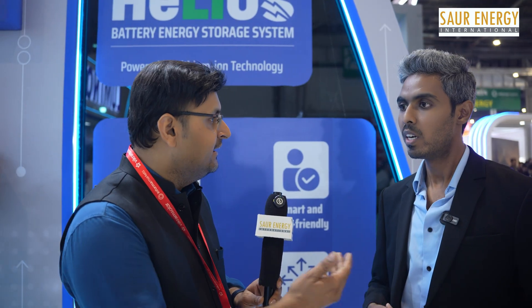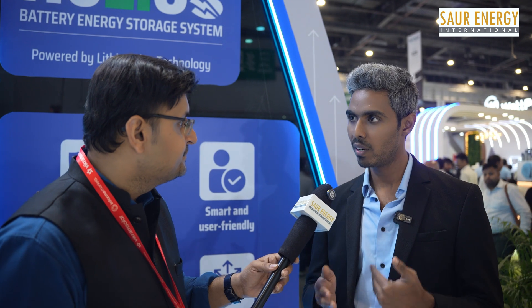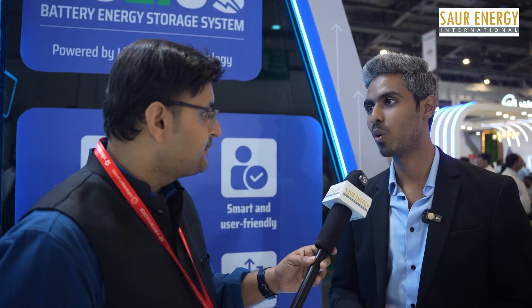For the residential and C&I market, both technologies coexist — lithium-ion as well as lead acid. When loads are as low as 500 watts to one kilowatt in small homes, lead acid still has a lot of advantages. In metro markets where you don't have much real estate space and want an all-in-one solution, lithium takes its place. Up to 30 kilowatt, there is a good play between lead and lithium, and we hope both technologies go hand in hand.